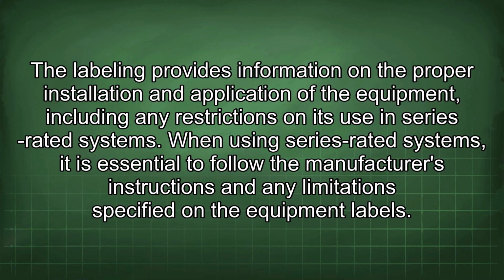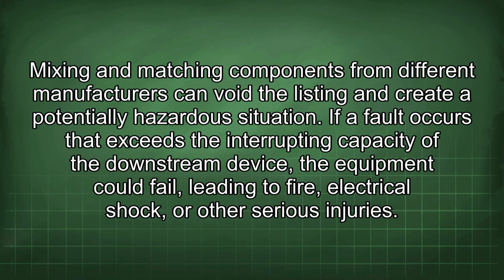series-rated systems. When using series-rated systems, it is essential to follow the manufacturer's instructions and any limitations specified on the equipment labels. Mixing and matching components from different manufacturers can void the listing and create a potentially hazardous situation. If a fault occurs that exceeds the interrupting capacity of the downstream device, the equipment could fail, leading to fire, electrical shock, or other serious injuries.